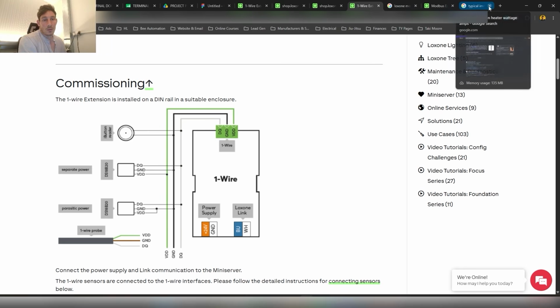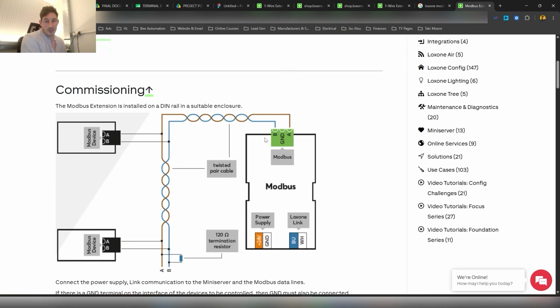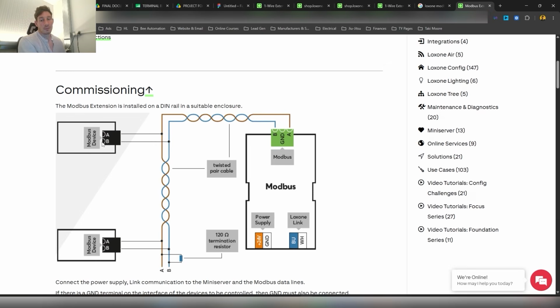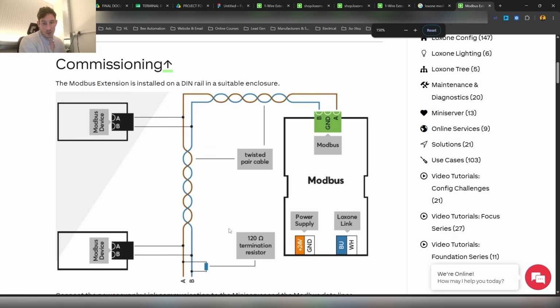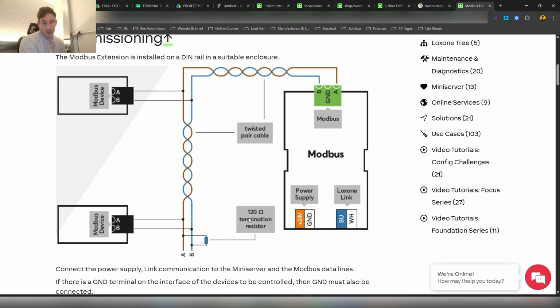And then the Modbus device, pretty straightforward - we've got A and B. This is our blue cable, our blue twisted pair, going out from A and B to our Modbus device, which in this case is that Eastron energy meter. You can see here also that on the final device, on the line, you should use a 120 ohm resistor - similar to the Loxone link communication.